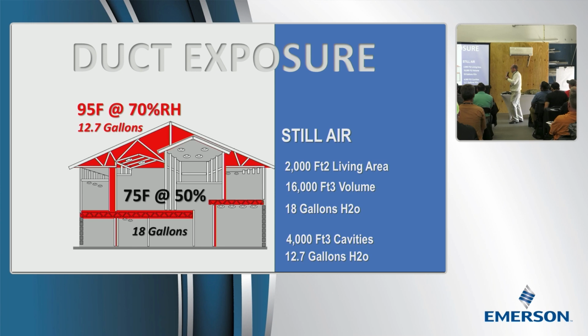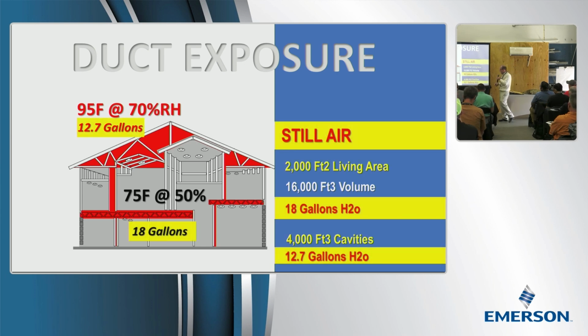All right, let's talk about the exposure moving these molecules. Still air is pretty harmless stuff, so here's an example. We've got still air in the attic space at 12.7 gallons. We've got still air in the interior part of the house at 18 gallons. Is 18 gallons of moisture in the air uncomfortable? Well, only if you're uncomfortable at 75 at 50, because that's what it is. So yes, there's moisture in the air, but my point is it doesn't condense until it moves. So here's what it does.